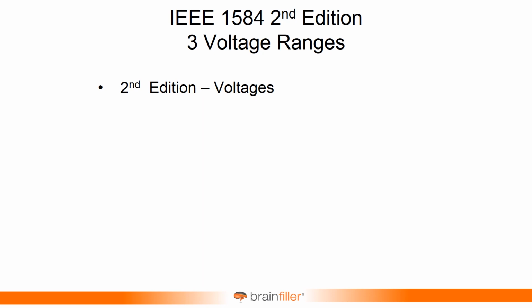So what happens with all the testing, we actually have three basic equations now based on 600 volts, and you actually pick a 600 volt model or 600 volt equation, or 2700 volts, kind of a mid-level, or up to 15 kV that was actually tested at 14,300 volts. So there are three equations, and you might think, well, that's not much of an improvement. You had two before. Well, these three equations are for everything. For the arcing current, for the incident energy, and for the arc flash boundary. Plus, this is what's called the intermediate, or I refer to it as the initial calculation.